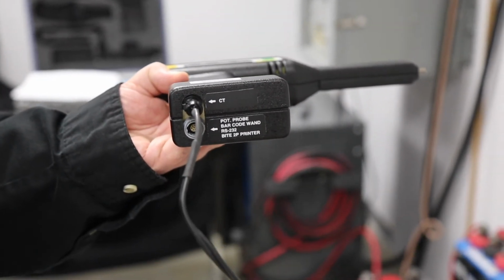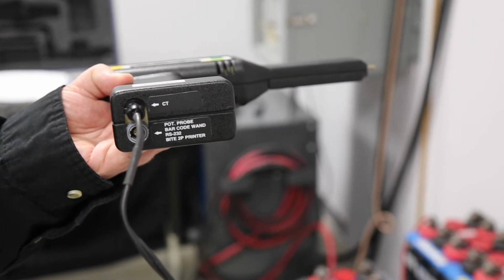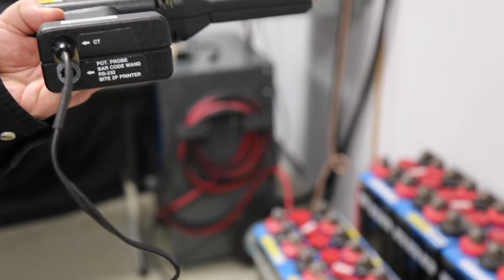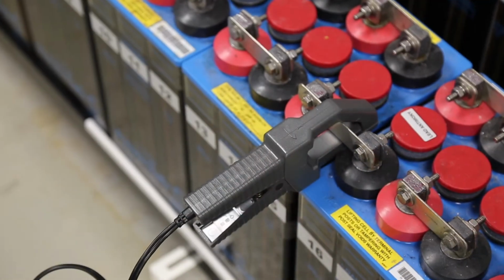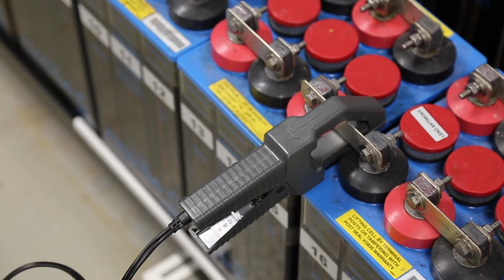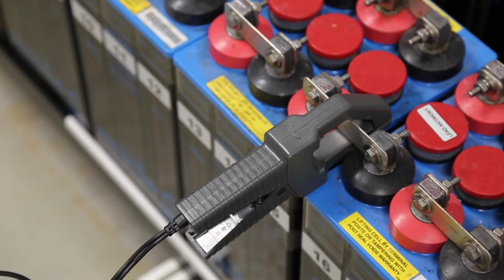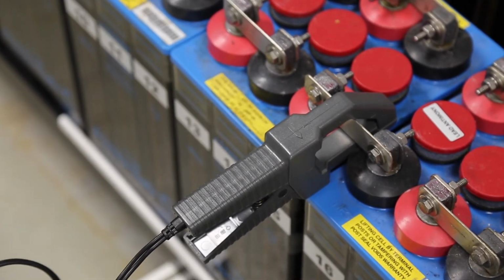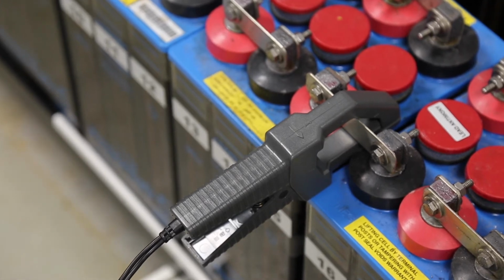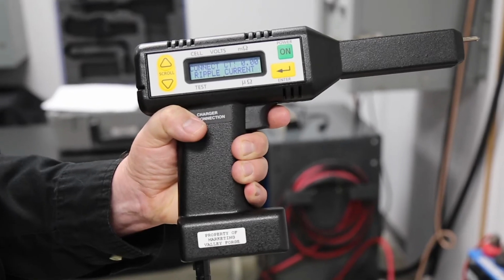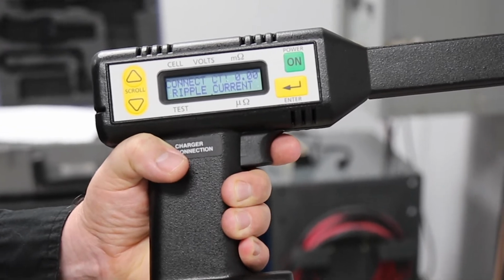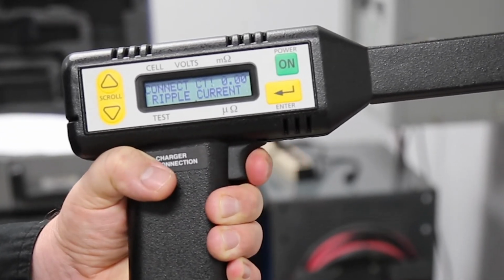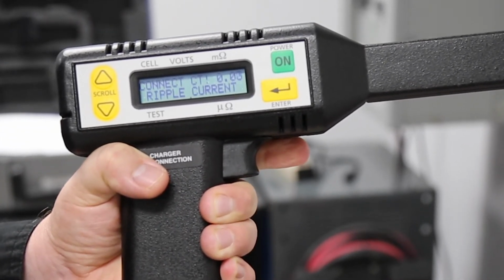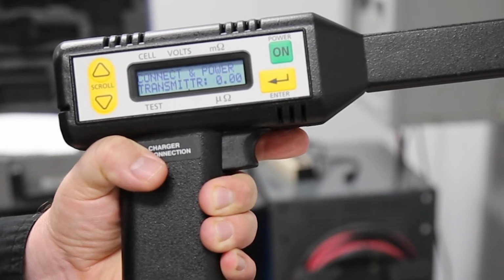This will allow me to measure the ripple current in the string. If the ripple current exceeds about 5 amps per 100 amp hour capacity of the battery, then this is a problem. It's typically a sign of a bad rectifier of the charger. In this case, we can see I have no ripple current, so I'll pull the trigger to save the reading. The receiver now prompts me to connect and power up the transmitter.